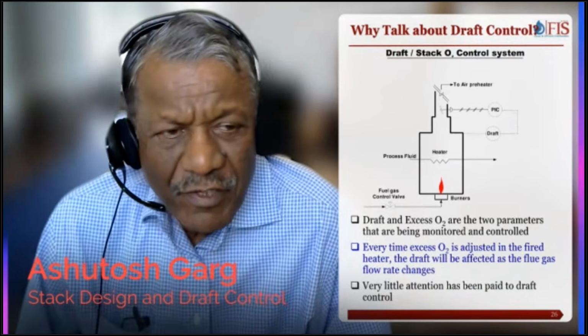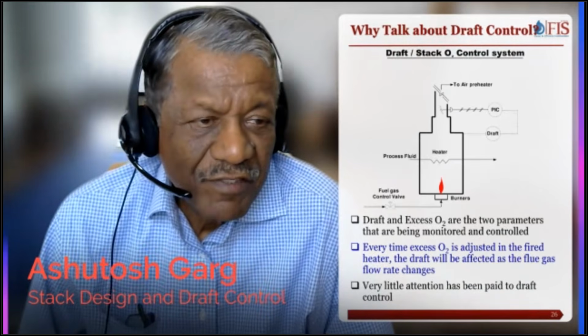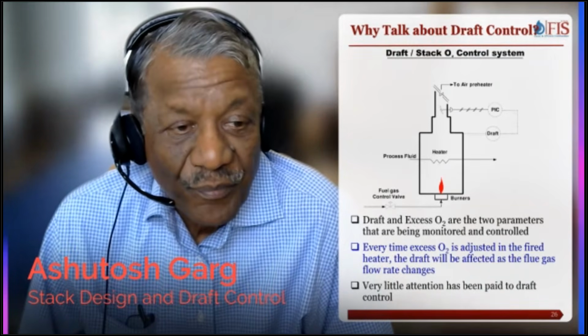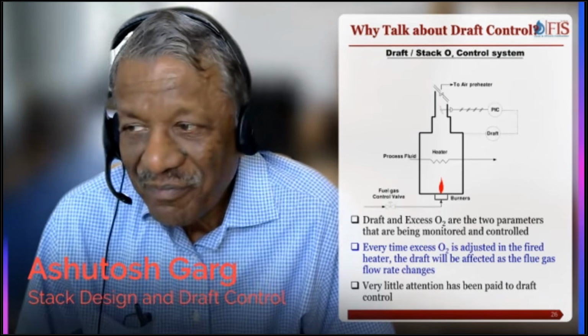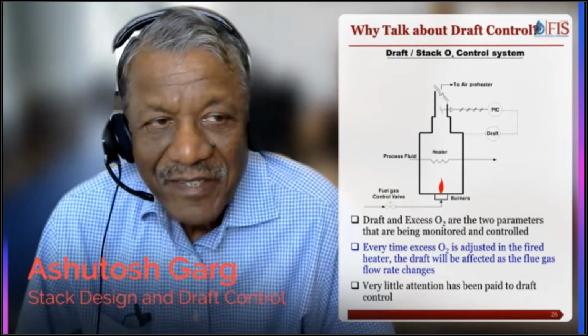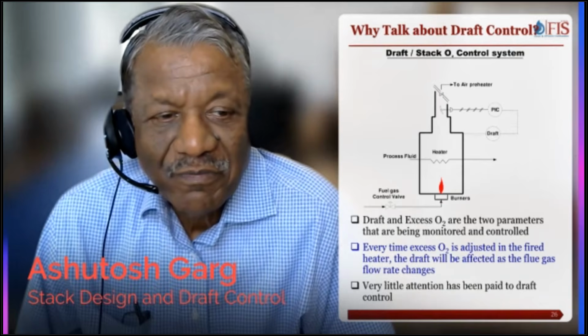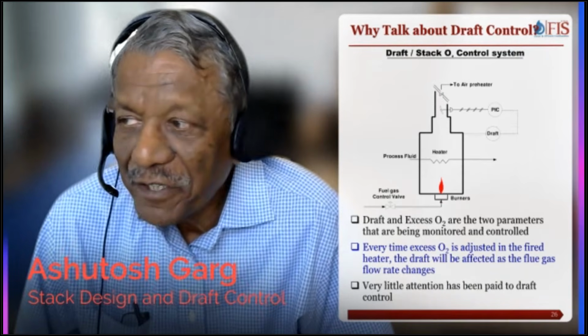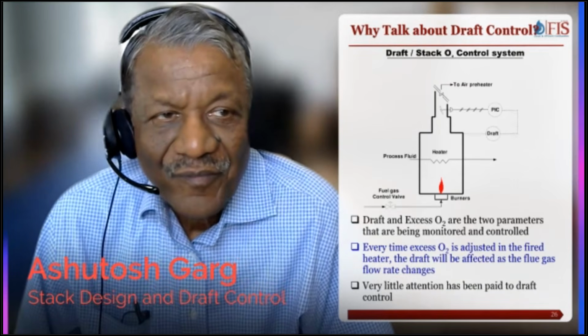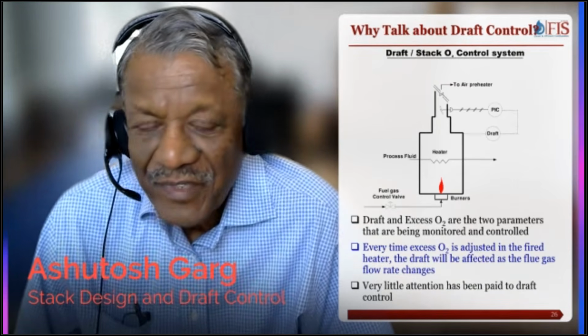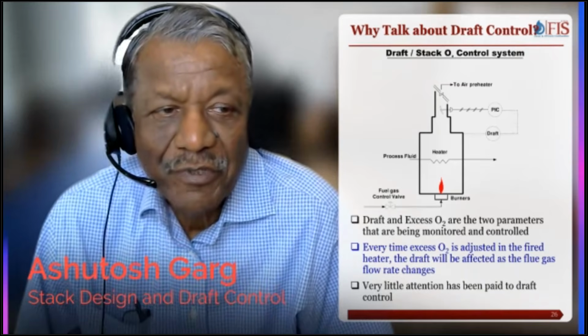So why are we talking so much about draft control? The reason is there are two important parameters in a fired heater. One is draft, the other is excess oxygen. Both are equally important.